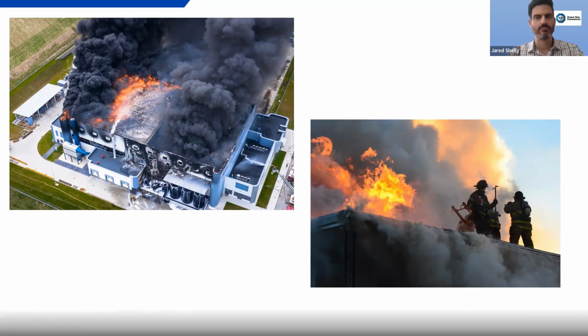And Jeff, what about you? Do you have any examples? Yeah, absolutely. In my 34 years, we've seen countless incidents of switchgear, switches, breakers, disconnects, you name it, critical equipment and assets failing, from switchgear that hasn't been properly maintained, potentially bus ducts that have accumulated dirt and debris, contaminants, moisture, all kinds of different environmental factors and corrosivity that will cause electrical or mechanical systems to fail.